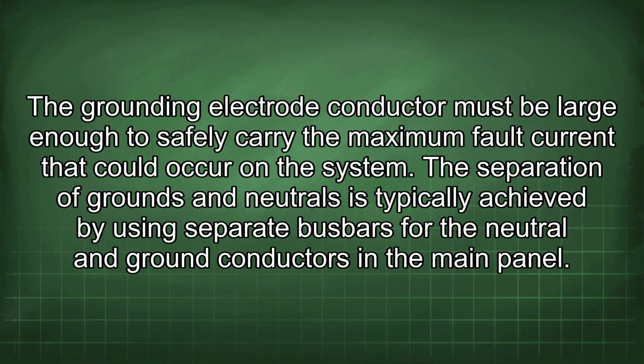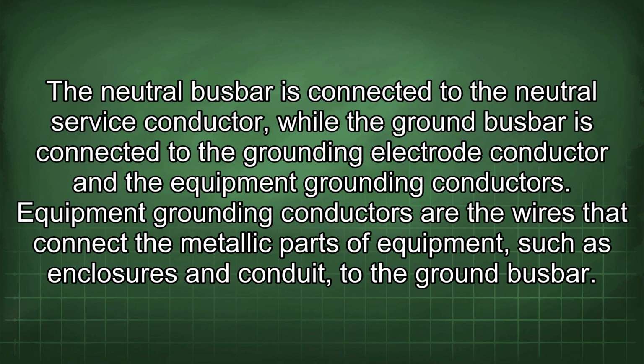The grounding electrode conductor must be large enough to safely carry the maximum fault current that could occur on the system. The separation of grounds and neutrals is typically achieved by using separate busbars for the neutral and ground conductors in the main panel. The neutral busbar is connected to the neutral service conductor, while the ground busbar is connected to the grounding electrode conductor and the equipment grounding conductors.